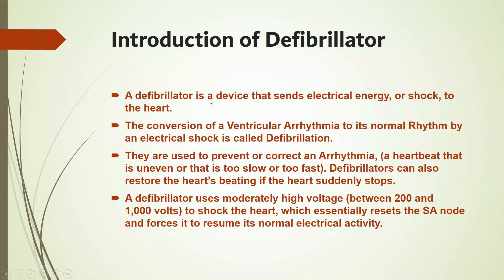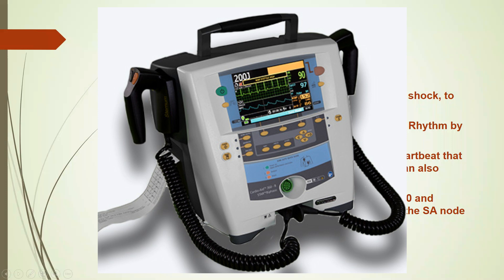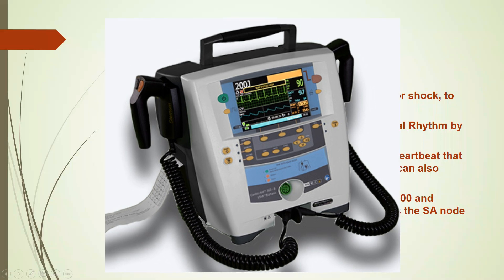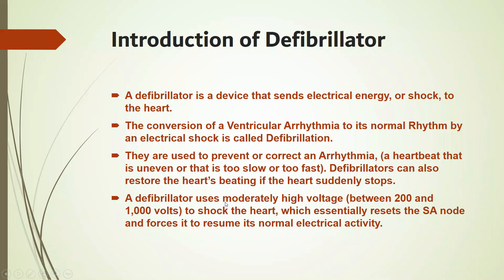A defibrillator is a device that sends electrical energy or shock to the heart. The conversion of a ventricular arrhythmia to a normal rhythm by an electrical shock is called defibrillation. They are used to prevent or correct an arrhythmia — a heartbeat that is uneven, too slow, or too fast. A defibrillator can also restore the heartbeat if the heart suddenly stops. Defibrillators use high voltage between 200 and 1000 volts to shock the heart, essentially resetting the SA node and forcing it to resume normal electrical activity.